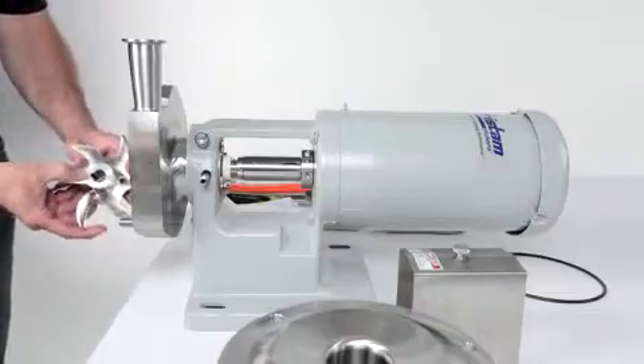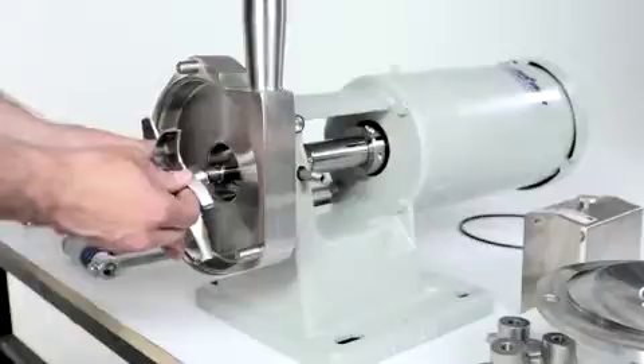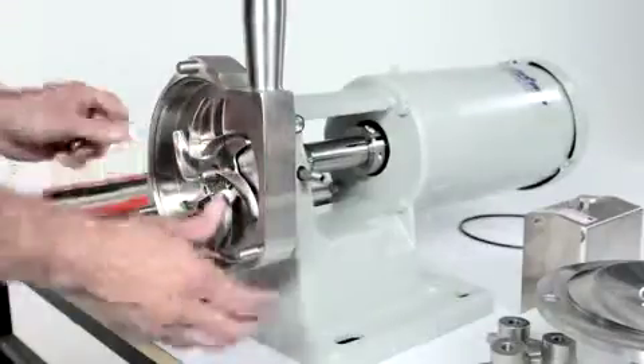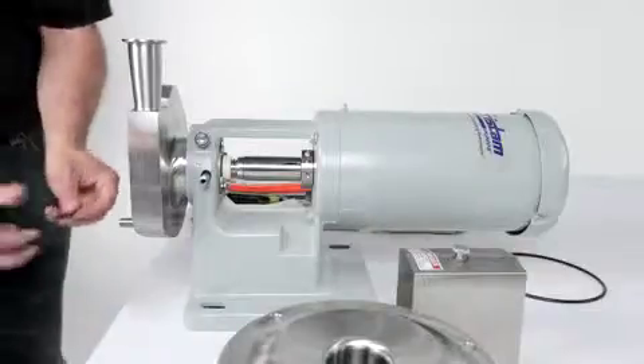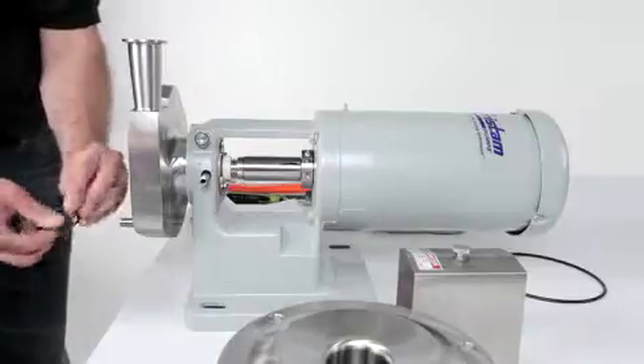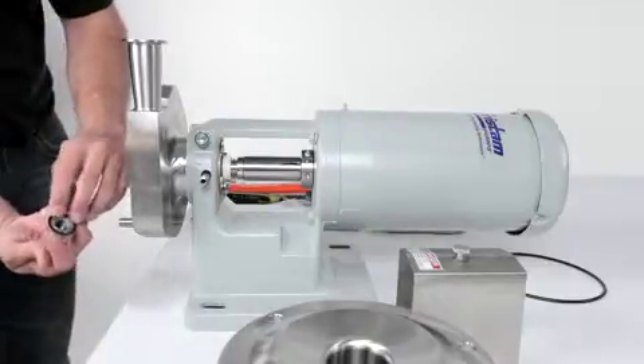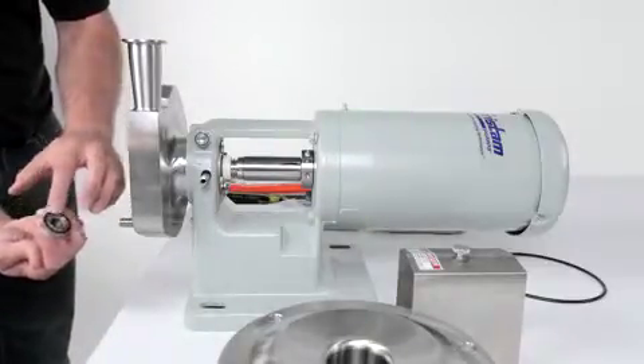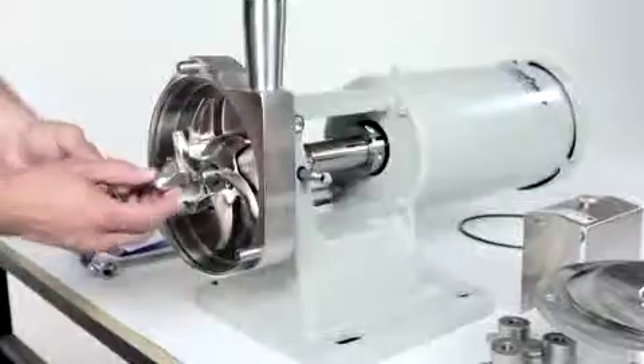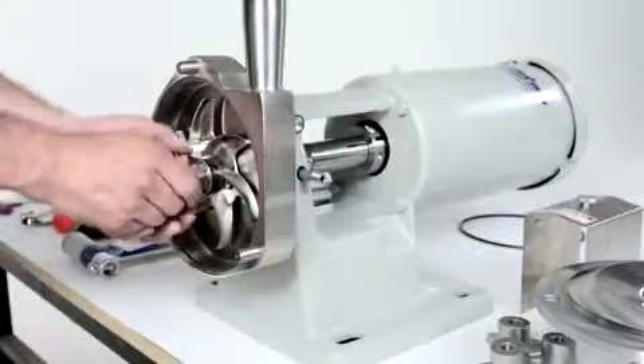Slide the impeller onto the shaft, making sure to align the keyway in the impeller with the key in the shaft. Lubricate the impeller nut gasket and place it onto the impeller nut. The raised face of the gasket will go into the groove on the impeller nut. Thread the impeller nut onto the shaft.